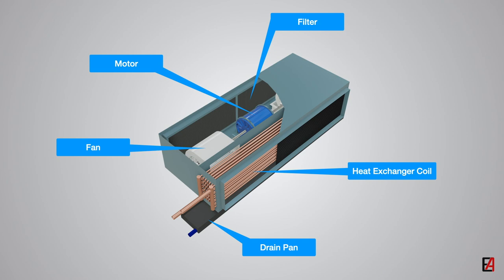In most of the fan coil units, the fan or blower is mounted before the heat exchanger coil. This type of fan coil unit is referred to as blow-through type where the fan is connected directly to the heat exchanger coil. Before the fan is an air filter, which filters the air before entering into the heat exchanger coil.